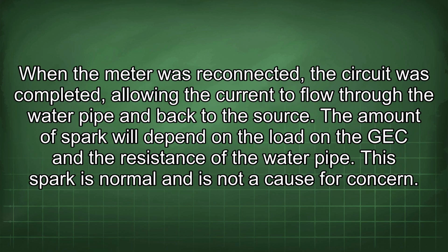When the meter was reconnected, the circuit was completed, allowing the current to flow through the water pipe and back to the source. The amount of spark will depend on the load on the GEC and the resistance of the water pipe. This spark is normal and is not a cause for concern.